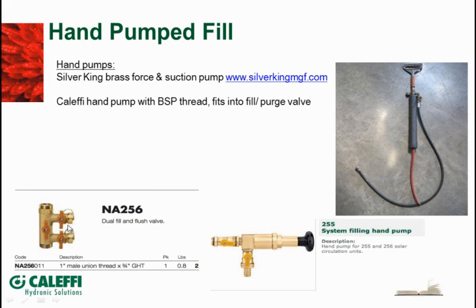Then it also gives you these little caps that you can cap it off, so when you're all done, you put that cap on, tighten it with a channel lock so somebody doesn't come down and think that's a place where you can get a drink of water someday and open it up. I've had that happen where the stonemasons come down and hook up to your glycol system thinking they're getting just regular tap water out of it to mix their concrete, and they're draining the glycol out of your system. So you laugh, but it does happen.